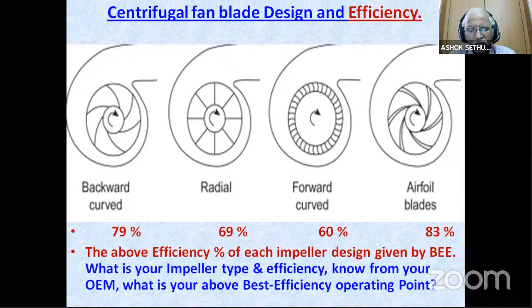The efficiency is not a single point efficiency, it's a band of efficiency. You can see the right hand curve. It is an inverted umbrella type curve. For a given flow rate, what is the efficiency? You are getting a peak efficiency only at one point. There you have to make your system match the efficiency. You have to design the system to get the best out of the blower for the given system.